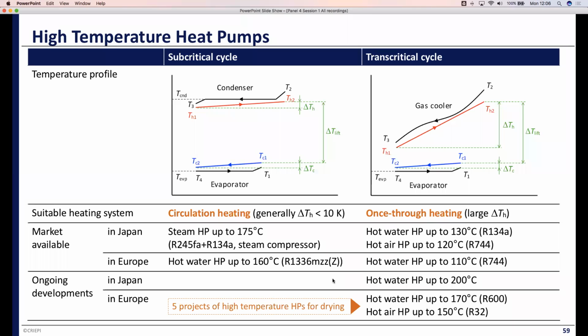On the other hand, the transcritical cycle is used when the heat sink temperature grade is relatively large, because the heat transfer irreversible loss from refrigerant to heat sink can be reduced. This cycle is suitable for once-through heating systems. In many cases of drying processes, the transcritical cycle would be better because the heat sink temperature grade is relatively large due to heating fresh air.